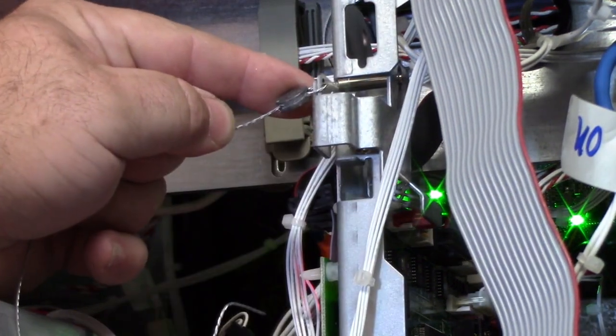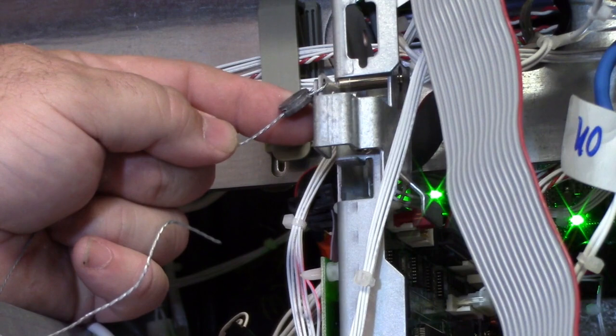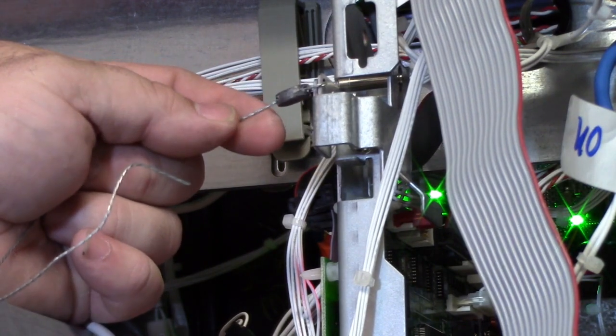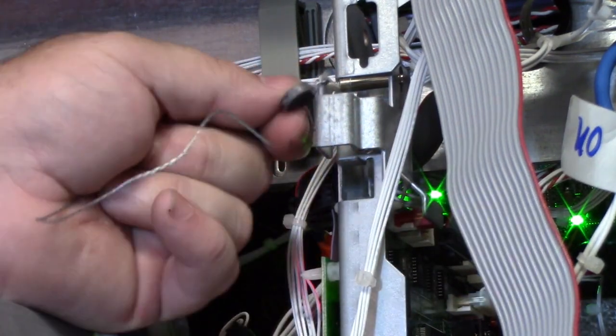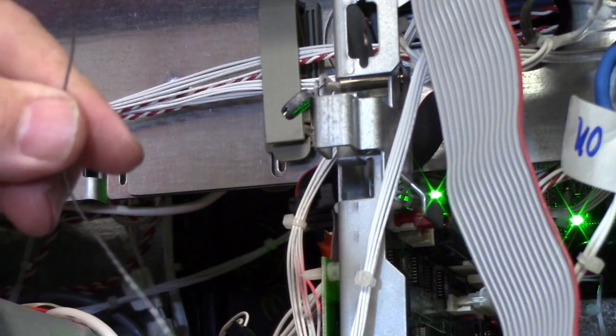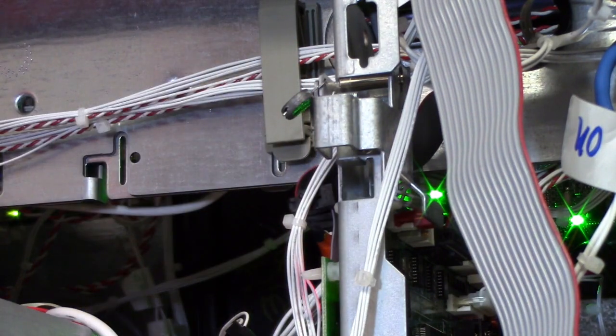When you crimp the lead seal, make sure that you can read your initials or your truck number, whichever seal identifies your truck as your truck. Use the side cutters again to cut that off so you don't have a bunch of loose wire hanging around inside the pump. Throw that in the trash.